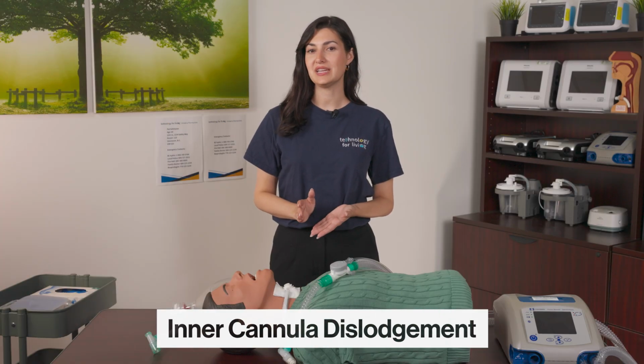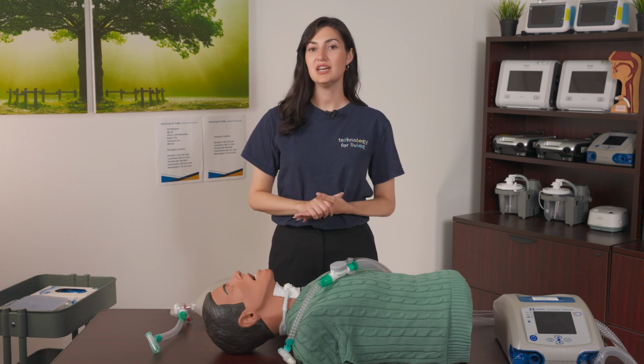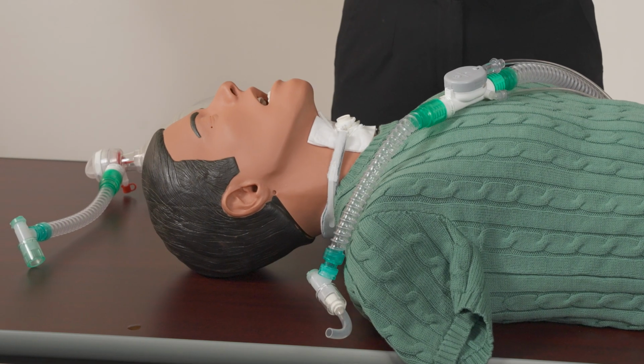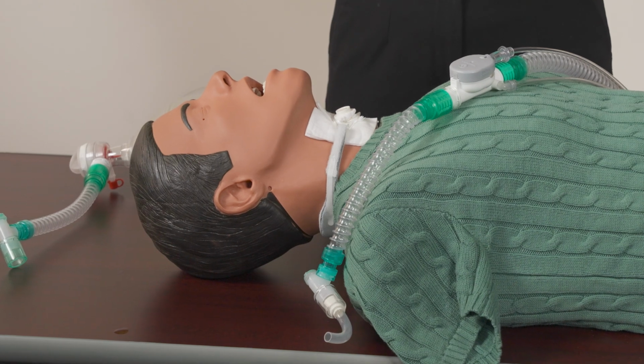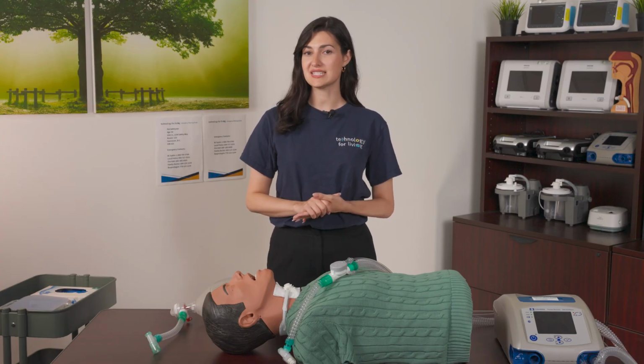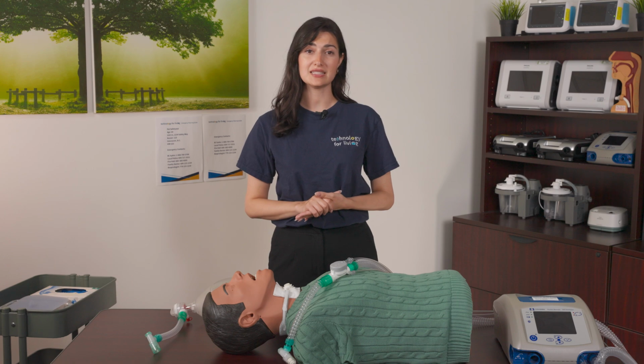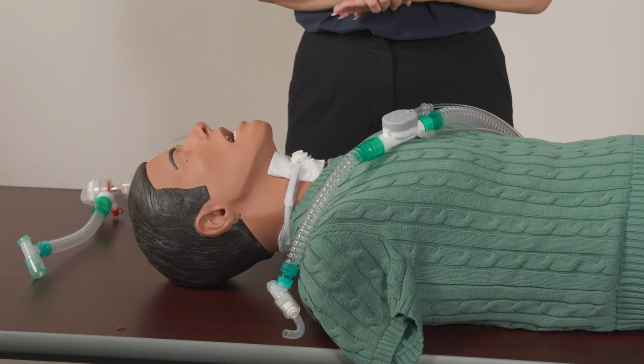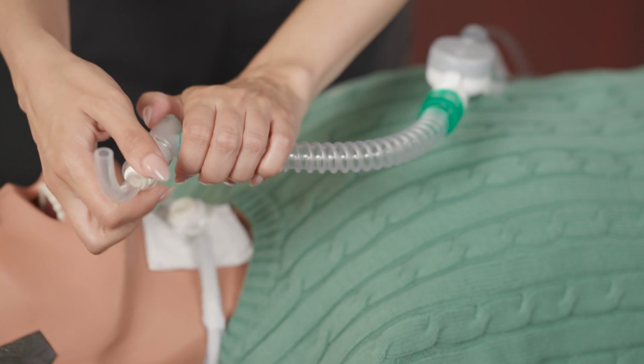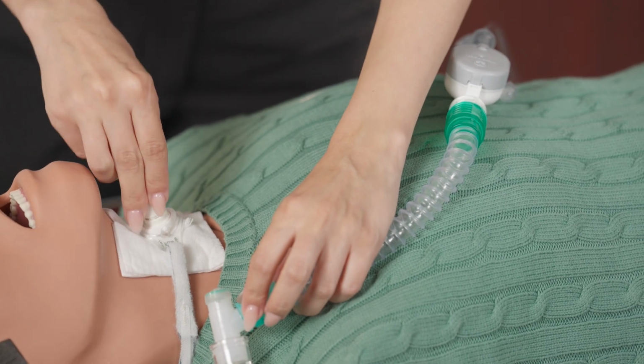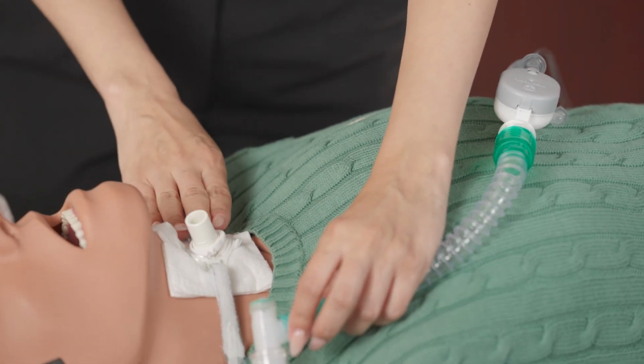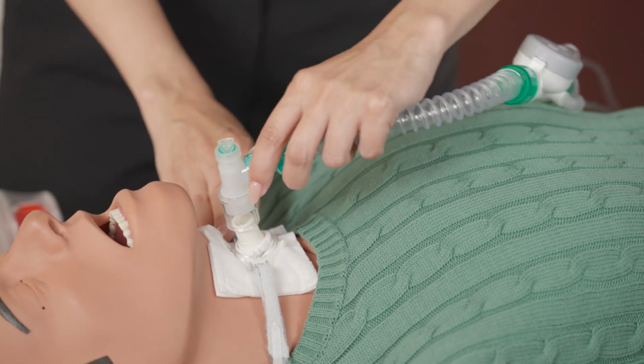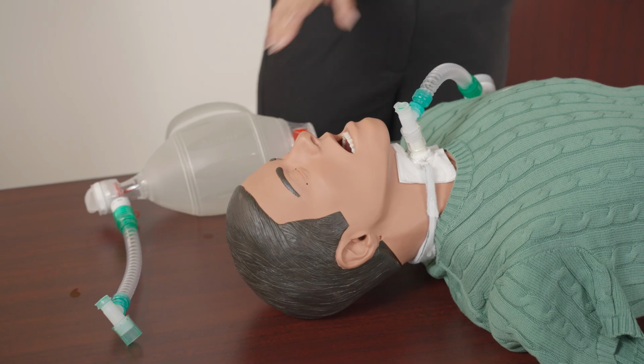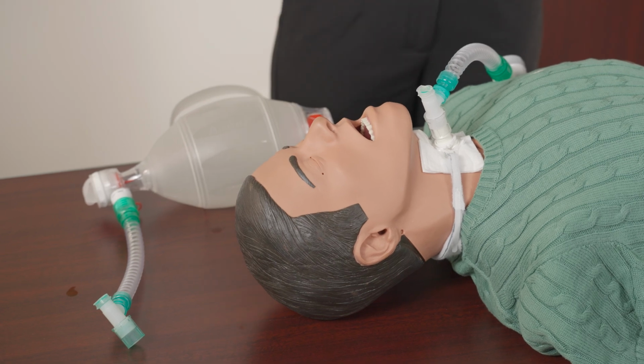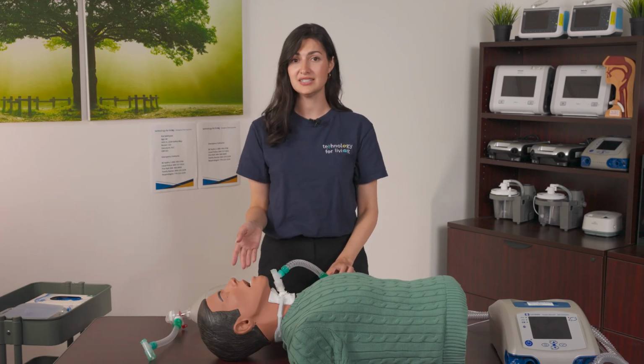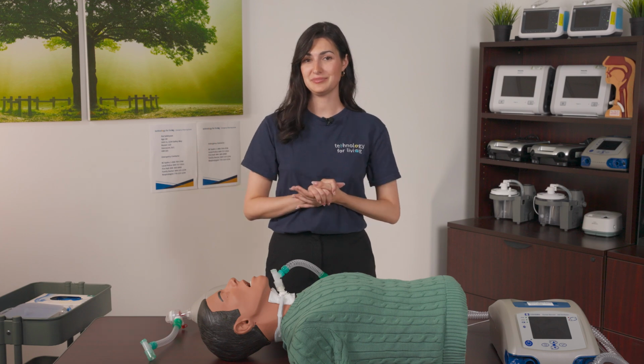If the ventilator is alarming and the member is trying to get your attention, you may see something like this. The inner cannula was not twisted and locked into place properly. This will cause a low pressure disconnect alarm after approximately 15 seconds. It's important to set the low pressure alarm correctly so that you are alerted if this situation occurs. Pull out the inner cannula and reinsert. Make sure that it's locked into place and reattach your member to the ventilator. Or you can grab your manual resuscitator and start bagging them. If this resolves the issue and the member is fine, then the situation has been resolved.